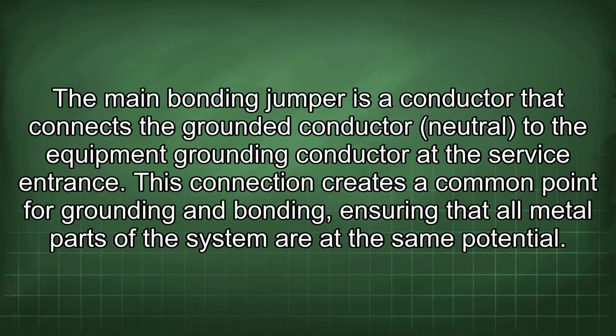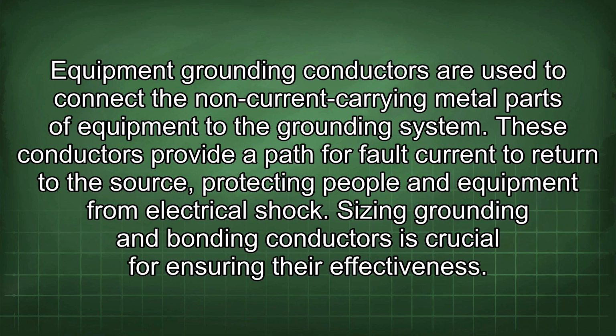The main bonding jumper is a conductor that connects the grounded conductor, the neutral, to the equipment grounding conductor at the service entrance. This connection creates a common point for grounding and bonding, ensuring that all metal parts of the system are at the same potential. Equipment grounding conductors are used to connect the non-current carrying metal parts of equipment to the grounding system. These conductors provide a path for fault current to return to the source, protecting people and equipment from electrical shock.